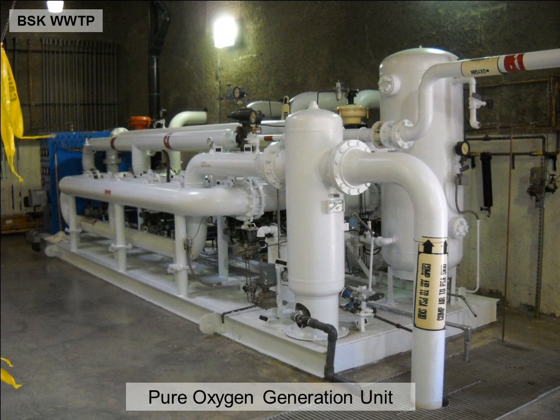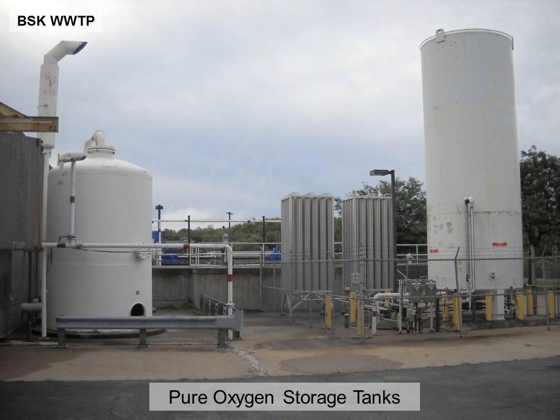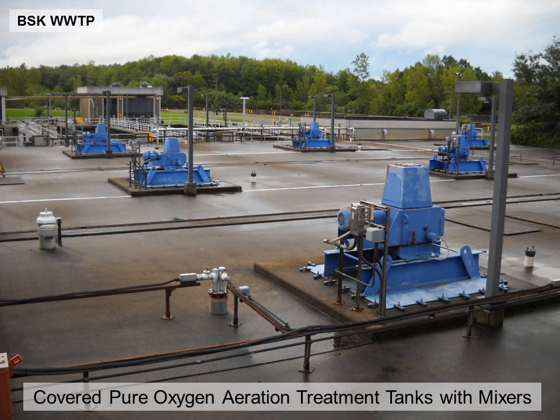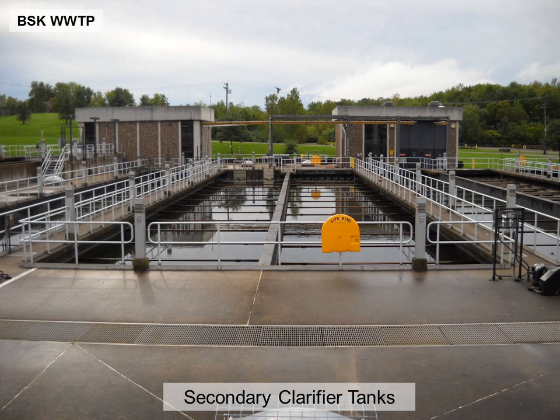Pure oxygen is generated on site and is used in the activated sludge process. Pure oxygen is also stored on site. The wastewater then flows into covered aeration tanks where it is mixed with pure oxygen to facilitate biological nutrient removal. The resulting mixed liquor from those tanks flows into a secondary clarifier for additional settling.